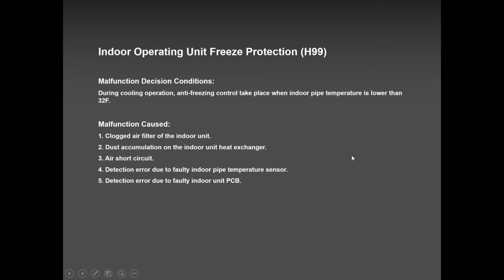So when there is not enough humidity, the coil is operating at a lower fan speed, the coil gets super cold and it shuts down on antifreeze protection. When the coil gets below 32 degrees Fahrenheit, the system shuts down. If it shuts down 4 times in less than an hour, the indoor unit will start flashing H99.